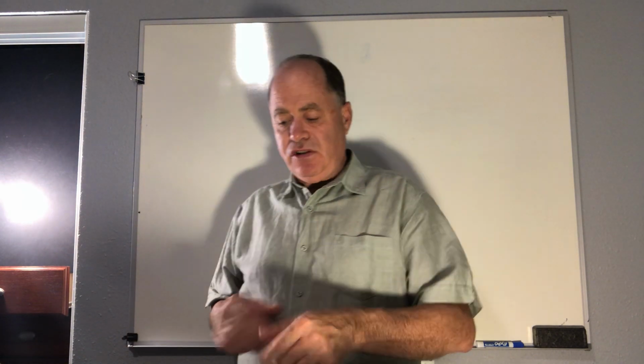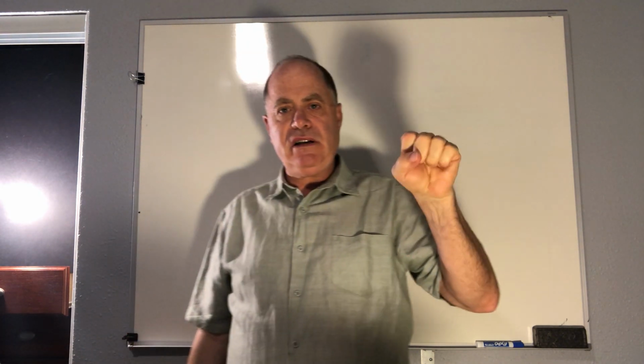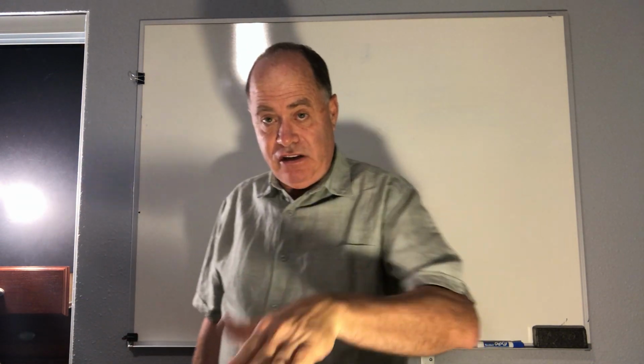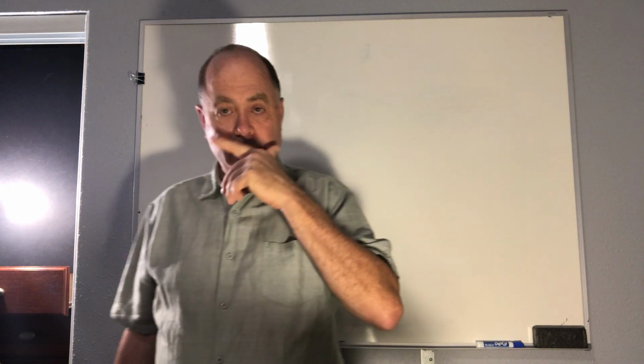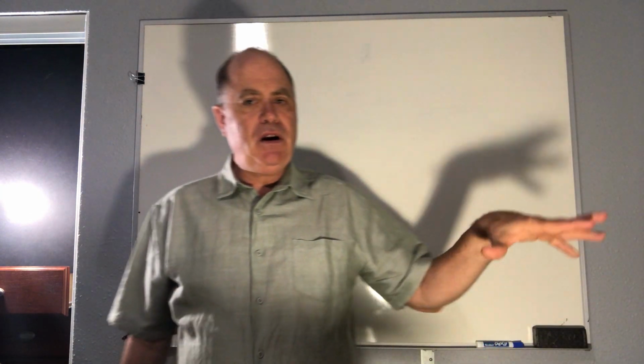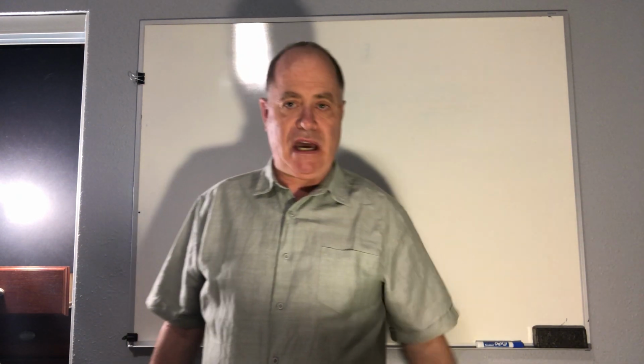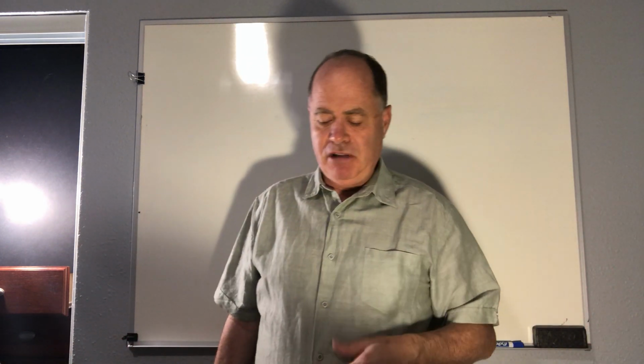And then if you remember from another lecture, for electric heat, I think it's 200 degrees, and then under the floor, like if the ductwork is going underneath a house to transmit the supply air, it's again 200 degrees. But generally, the maximum for everything is 250. That's a very old rule, and most manufacturers don't get near that. Again, they put their limit controls maybe closer to 160, something like that.